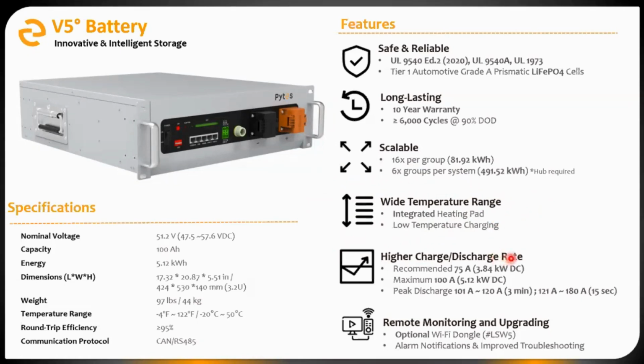Another big improvement on the V5 is a higher charge and discharge rate. Our first original battery had a 50 amp, half-C charge and discharge rate. The V5's improved rating is 75 amps charge and discharge per battery, about 3,800 watts of power. The battery can also achieve a slightly higher rate, up to 1C, which is 100 amps, or about 5 kilowatts of power you can put into or pull out of the battery.